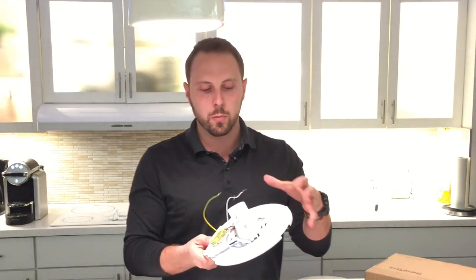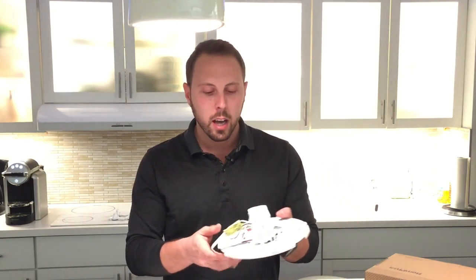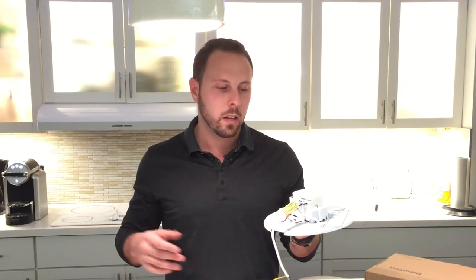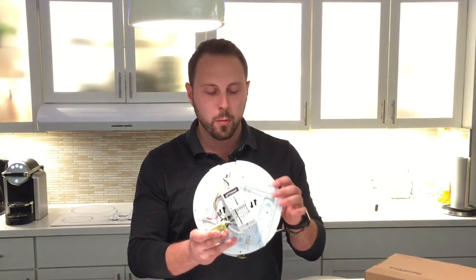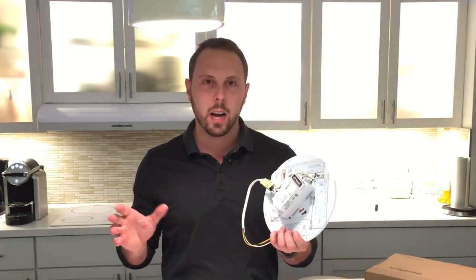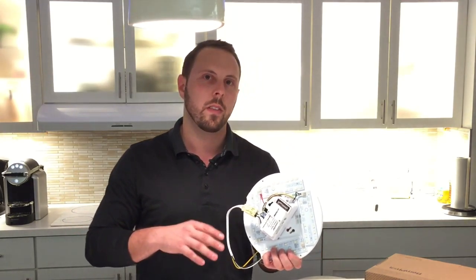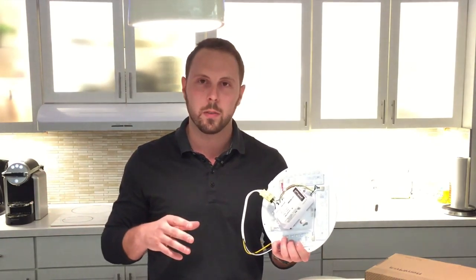When used as a retrofit to replace existing CFL lamps, circline lamps, PL lamps, or incandescent lamps — whatever may be in that existing fixture — it can retrofit anything from maybe one 13-watt CFL all the way up to double circuit lines. It's available in four different lumen packages from 900 lumens up to 3000 lumens, and it's extremely efficient at about 125 to 130 lumens per watt. For example, the 900-lumen disc is about 7 watts and the 3000-lumen disc is 27 watts.